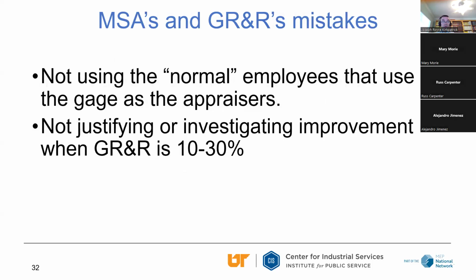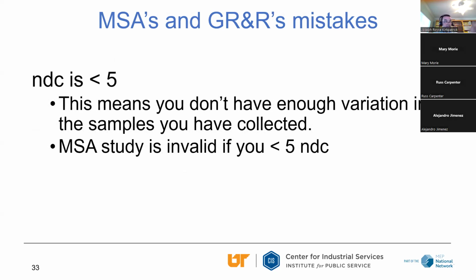Another error is not using the normal employees who use the gauge as appraisers. It shouldn't be just the quality manager, a supervisor, and the plant manager doing it because they're the only ones that have time. It should be done with the normal people that use the gauge day in and day out. Other errors are not justifying or investigating when your gauge R&R is above 10%. NDC has to be 5 or greater. Otherwise the MSA study, again, is invalid. There's not enough variation in the samples if the NDC is less than 5.